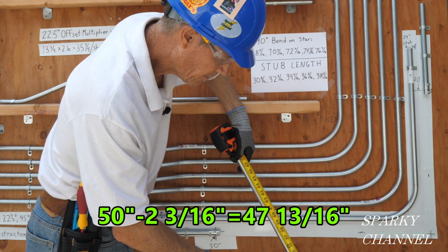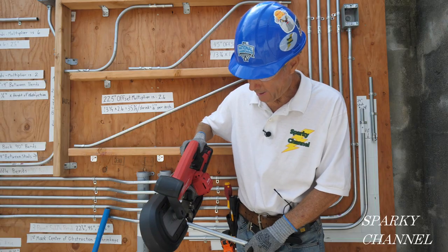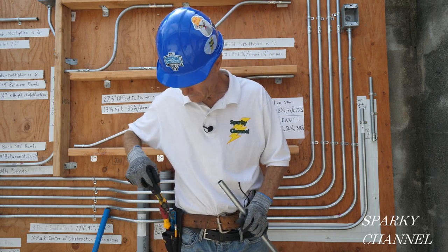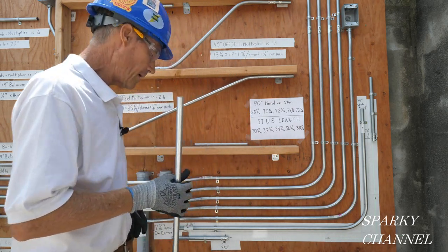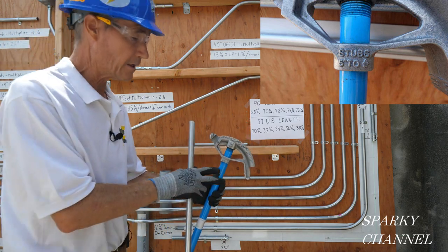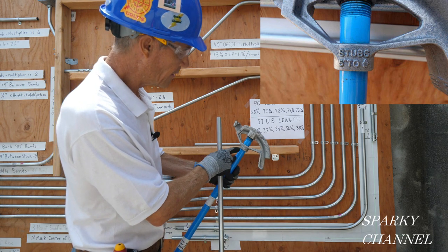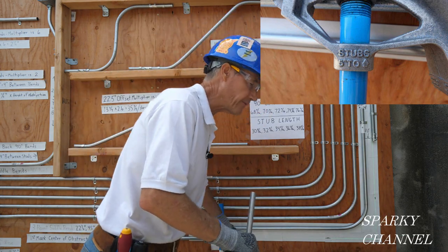I'm going to take this 50 inch piece of conduit, measure 47 and thirteen-sixteenths, and cut it with my bandsaw, then ream it out. We have a 20 inch stub over here. The bender says right on it: stubs five inches to arrow — that's on a half inch bender. On a three-quarter inch bender it's six inches. So with a 20 inch stub, we're going to make a mark at 15 inches.